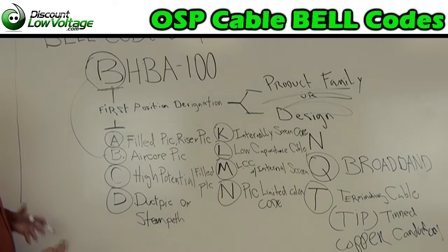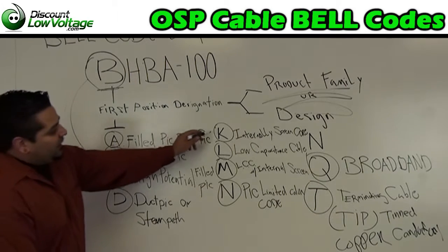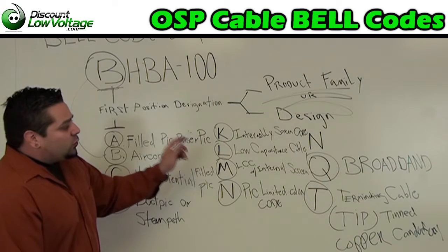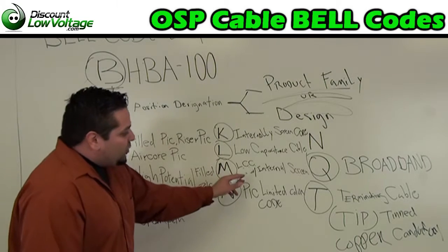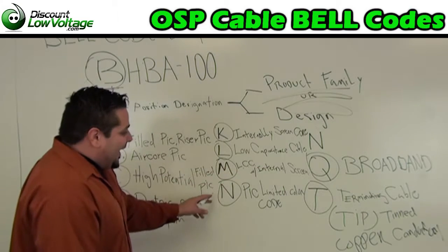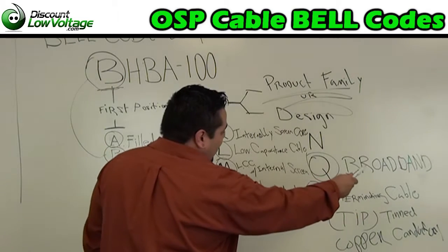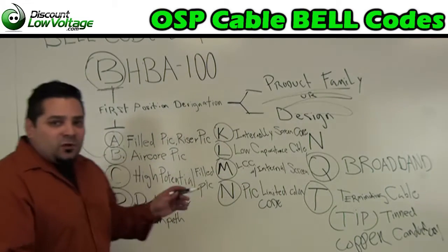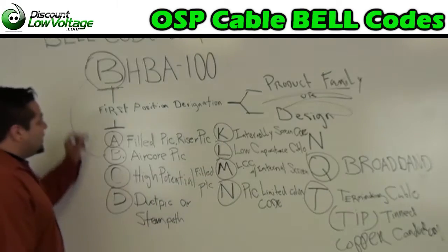C is a high potential filled PIC cable. D, duct PIC or steam path cable. K, internally screened core. L, low capacitance cable. M, a low capacitance cable with an internal screen. N, PIC limited color code cable. Q, broadband. T, terminating cable. TIP, tinned copper conductor. So B is what we have here, and this tells us our design of our cable.